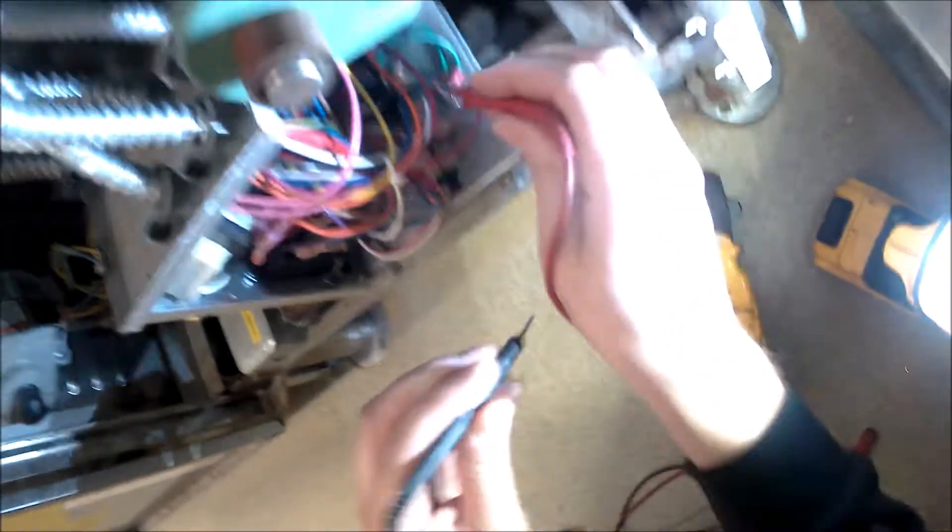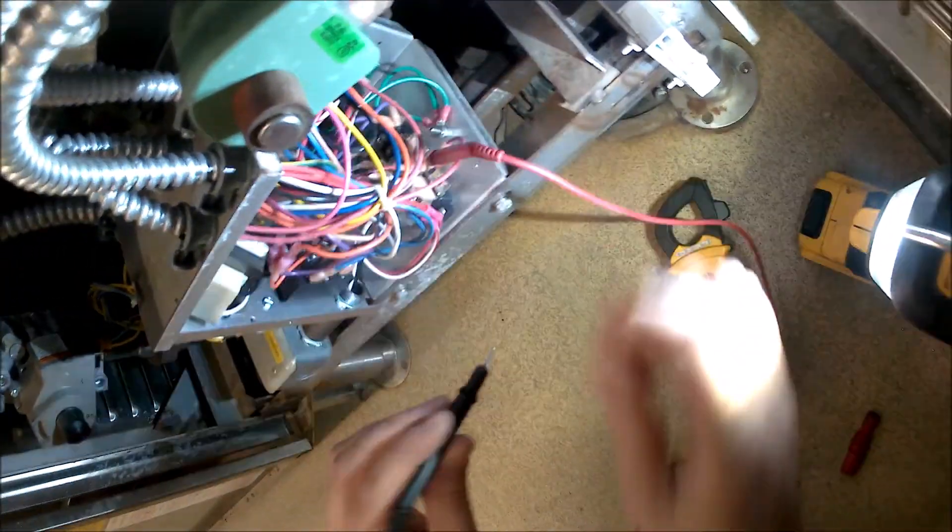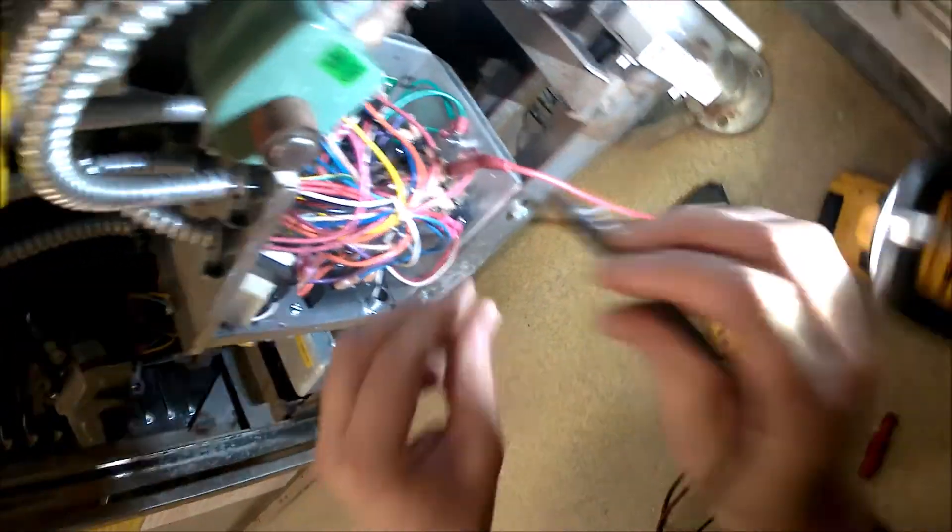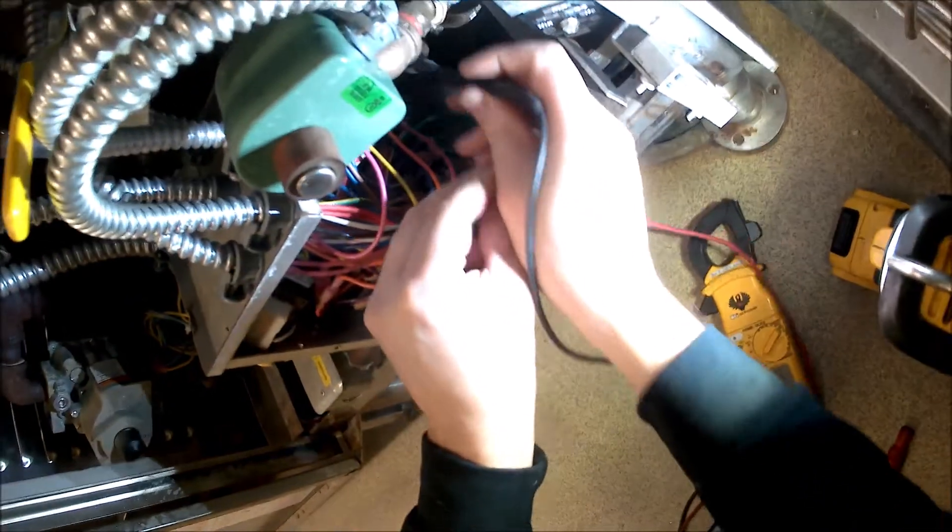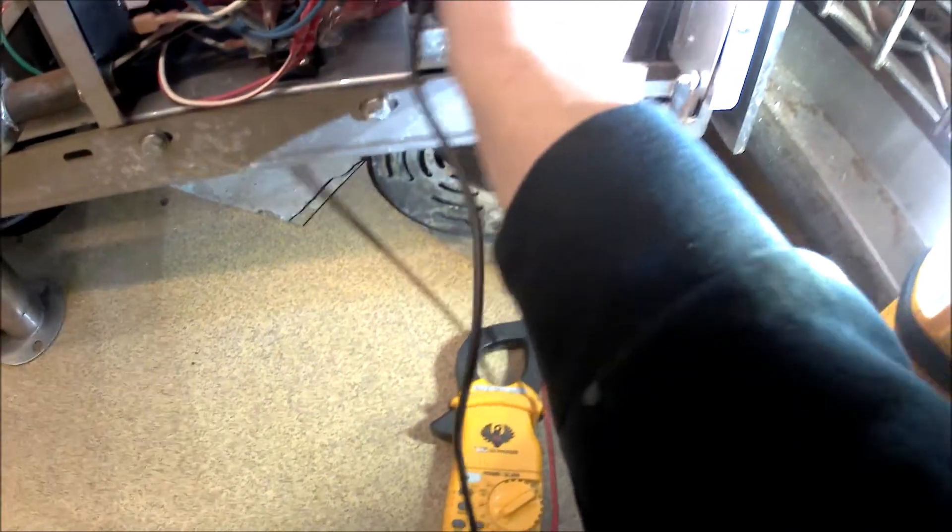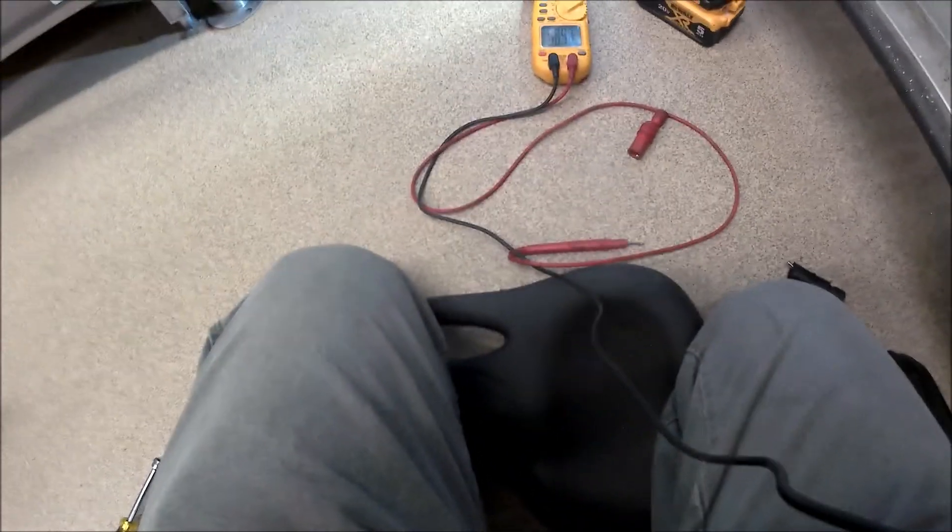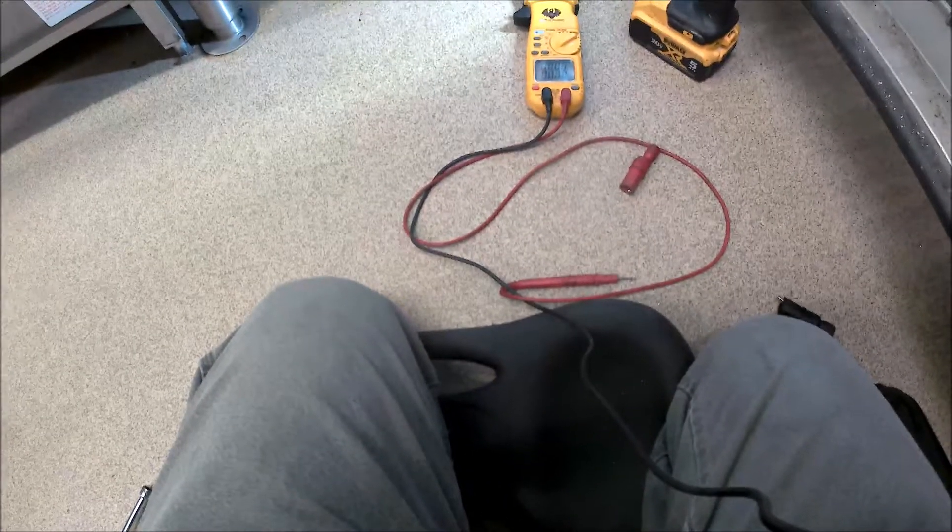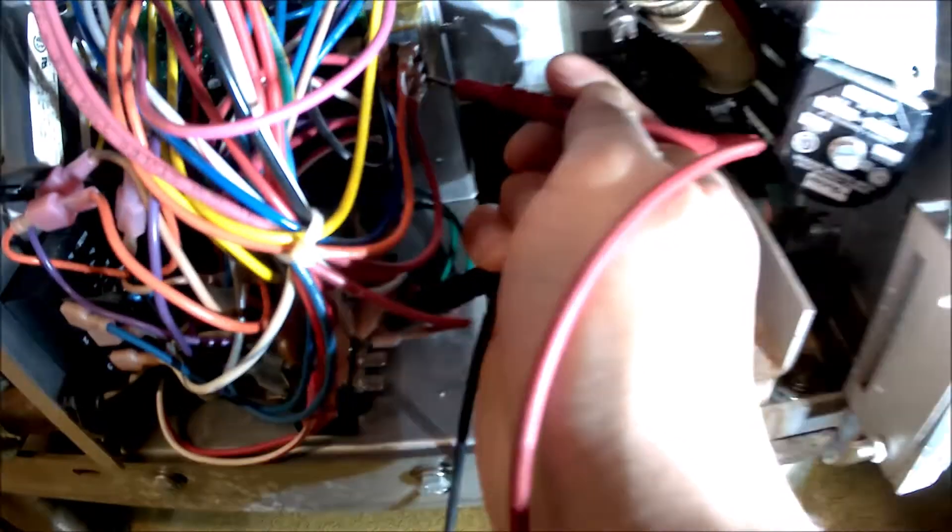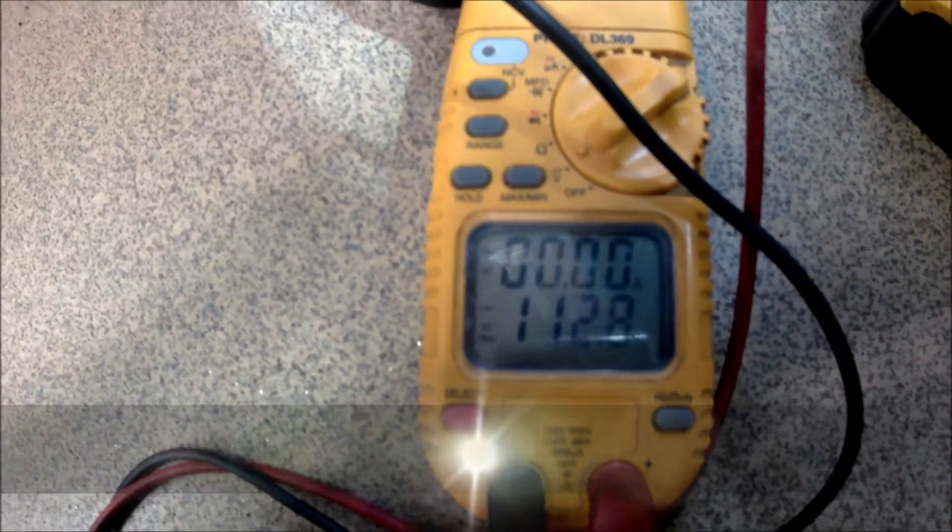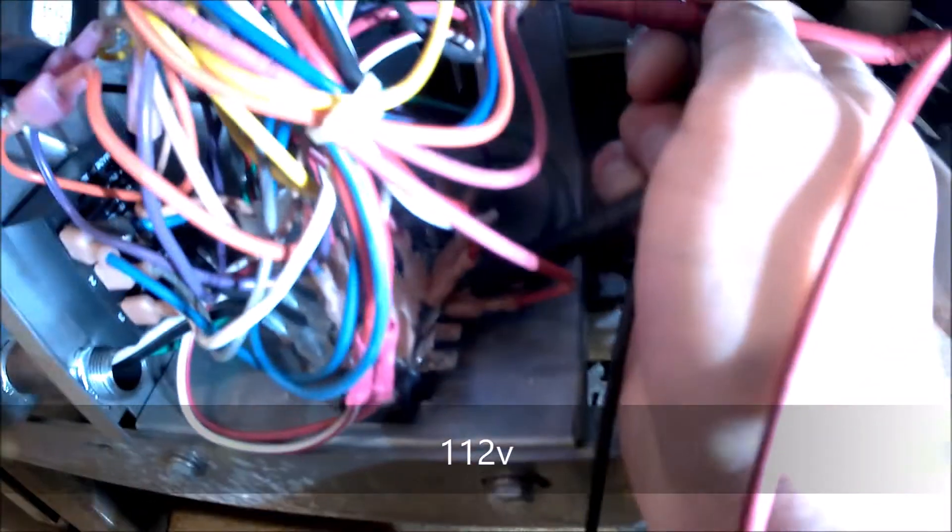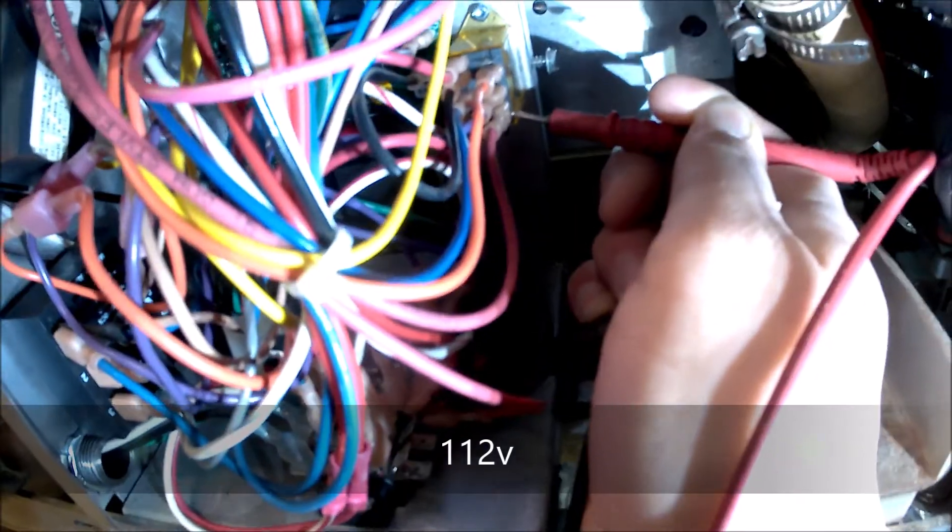Now I'm going to see if there's power going through the switch. I'm doing this live because if I shut off the unit it's going to drain all the water. I'm testing across - zero volts across would indicate a closed switch, voltage across would indicate an open switch. We're testing across, 112 volts across. This is telling me the float switch is open.